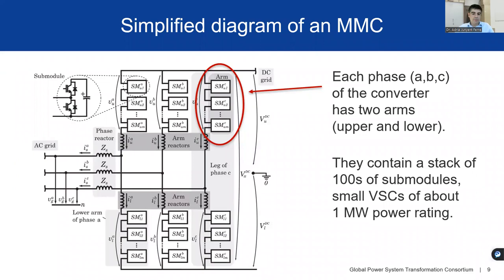This is how the circuit of an MMC looks. It's a three-phase AC-DC, DC-AC converter, bidirectional in power, with full control of active and reactive power. For each of the three phases, we have what we call an arm — we have the upper arm and the lower arm. In each of those, you have a stack, which is a series connection of a large number of small power electronic converters called submodules. Each submodule is about one megawatt of power rating with a voltage rating of a few kilovolts, and by stacking them in series, we reach the voltage ratings required for HVDC transmission.